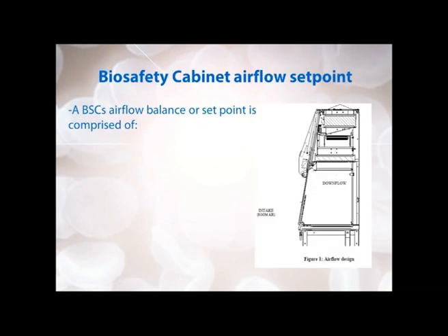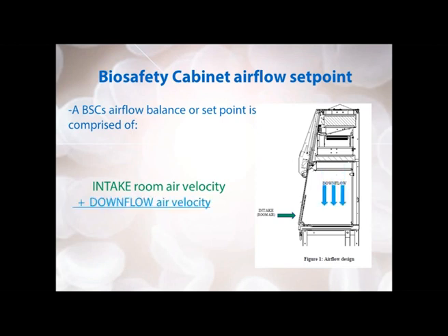In order to understand what intake air is, we're going to discuss the biosafety cabinet airflow set point. A BSC airflow balance or set point is comprised of two parts. First, you have the intake or room air coming in through the open front sash of the biosafety cabinet — when the sash is at its designated height such as 8, 10, or 12 inches. This is balanced with the amount of downflow air coming down through the HEPA filter and diffuser into the work area. These two speeds make up the airflow set point.